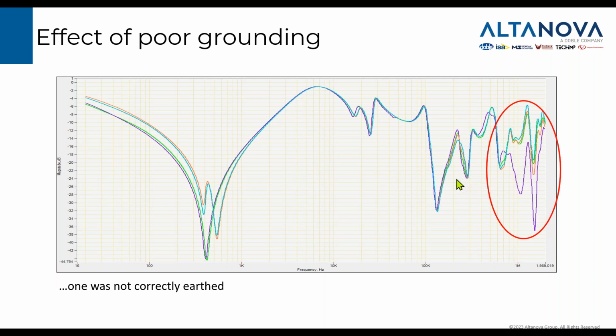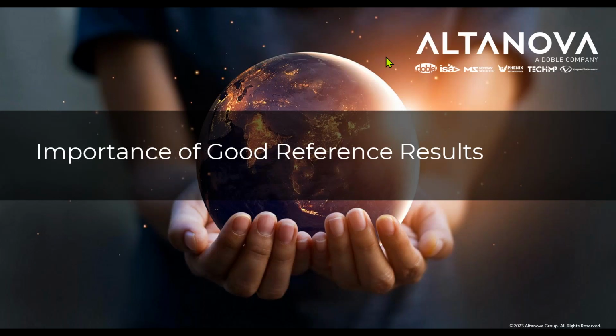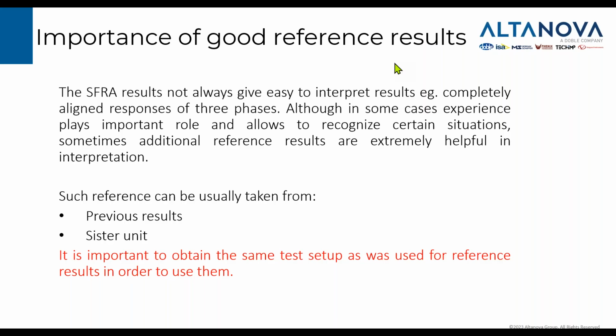So when I retested with my leads, test lead connected to different points, one of these three traces here is the same phase, but connected to ground in the proper place. So these were influencing factors. As we know already what to look for when we test the transformer, and we know what can affect our traces when we measure them, we would like to use some reference if it is available. It's not always available, but when it is, it is highly valuable because it can greatly increase confidence in our interpretation.